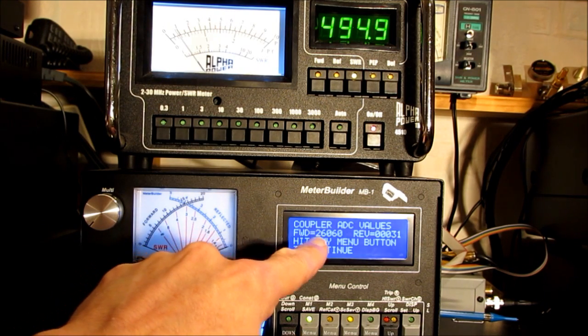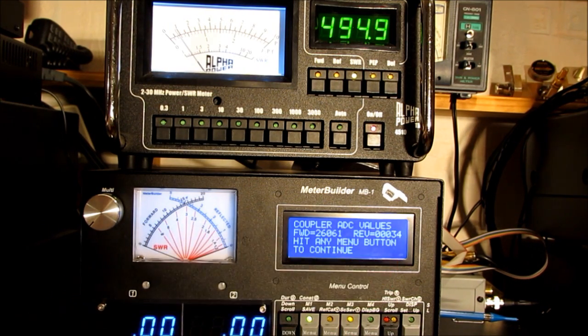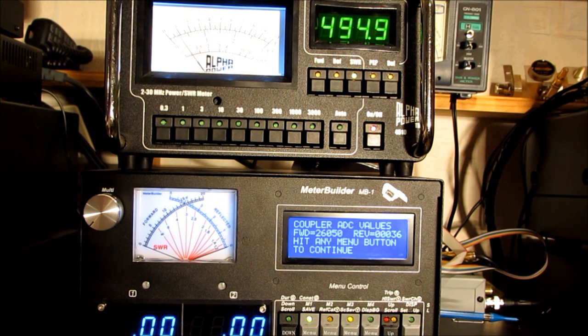What I'm seeing here now is the forward and reflected ADC value. This is the value being read in by the ADC, and you can see as I reduce the power, the ADC value changes as well. But the point is, for maximum resolution and sensitivity, I want to get that number up to roughly 30,000. So without overstressing the coupler, let me power this down for a minute, and while transmitting 500 watts, I'll go to the side panel pot for coupler 4, the forward pot, and adjust it to get that number up to 30,000.